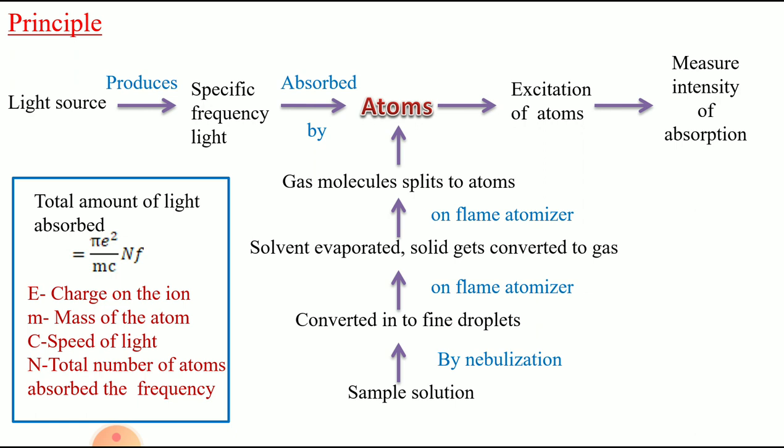The main aim of the flame is to convert the sample solution and molecules into atoms. From the light source, a specific frequency light is produced, which is absorbed by the atoms. When the atoms absorb the light, they undergo excitation and then return to their ground state. During this process, we can measure how much radiation is transmitted or absorbed. The total amount of light absorbed equals pi times e squared divided by mc, times nf, where e is the charge on the ion, m is the mass of the metal, c is the velocity of light, and n is the total number of metal atoms absorbing the specific frequency line.